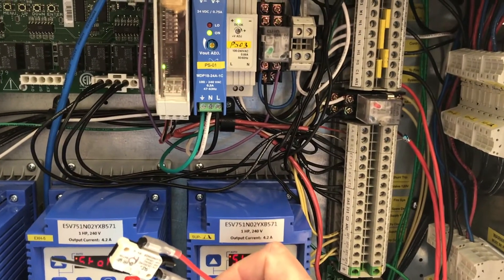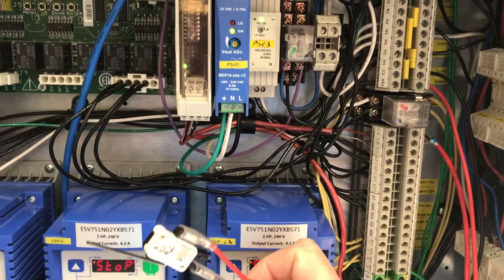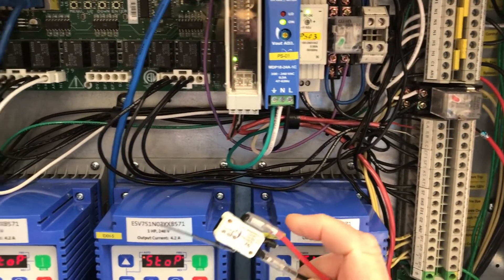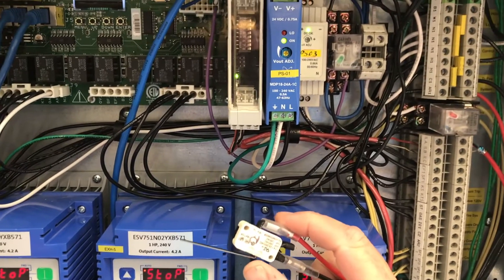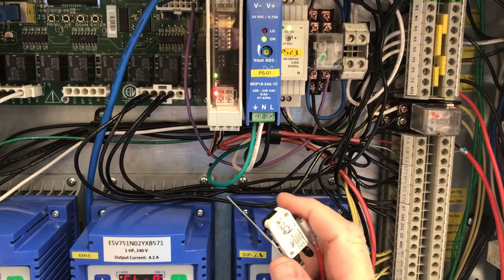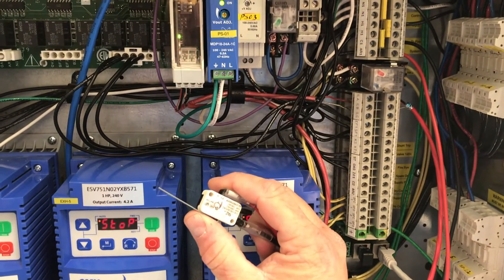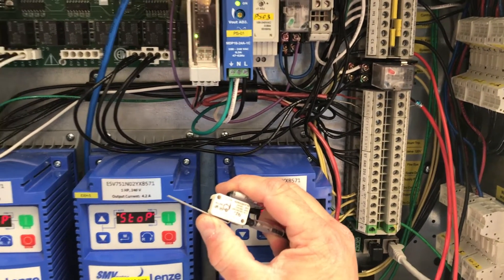Now I'm going to demonstrate what happens when the hood is turned off and the Ansul system is activated. The Ansul system will be activated and it will trigger operating the microswitch. We're going to use our demo switch here to demonstrate this. If we operate the switch, what you'll notice is the exhaust fans — the VFDs for the exhaust fans — will start to ramp up.